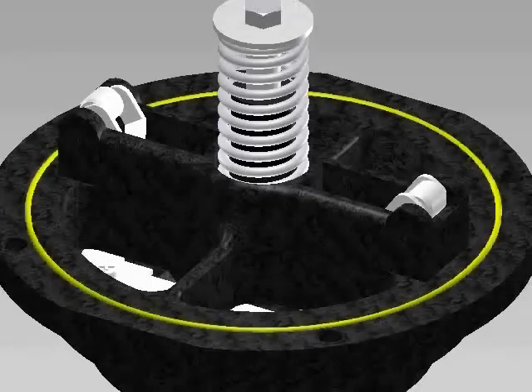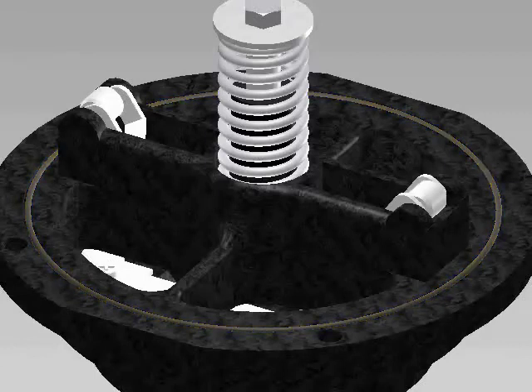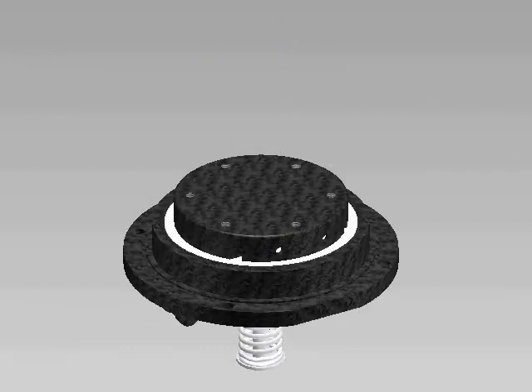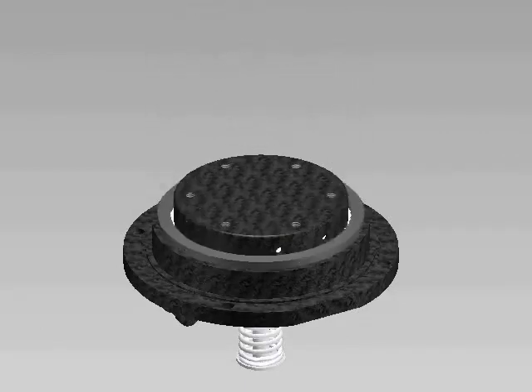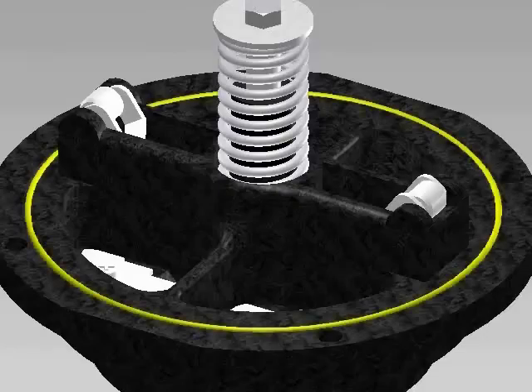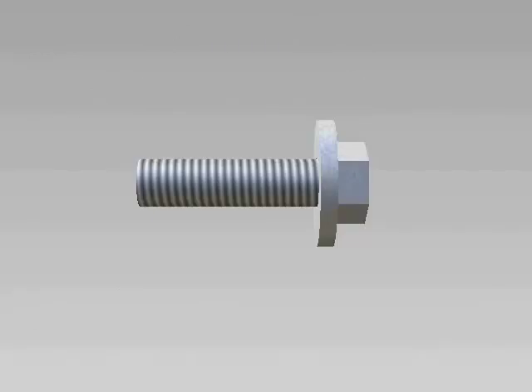Inspect the O-ring and the groove on the seat for debris or damage. Replace any damaged parts. If you are installing a repair kit, replace the seal ring, seat O-ring, and bolt O-rings.